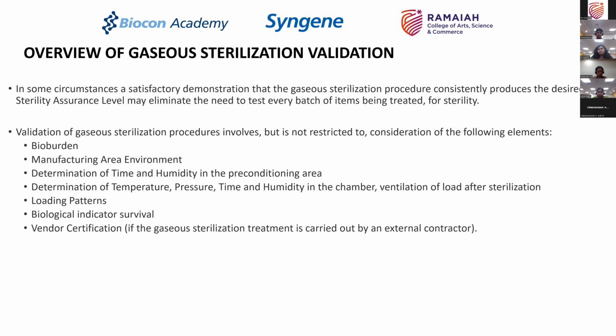Remember that gaseous sterilizations are dependent on humidity of the environment and the time. So what is the humidity at which you are injecting the hydrogen peroxide, for example? Those are very, very important aspects.